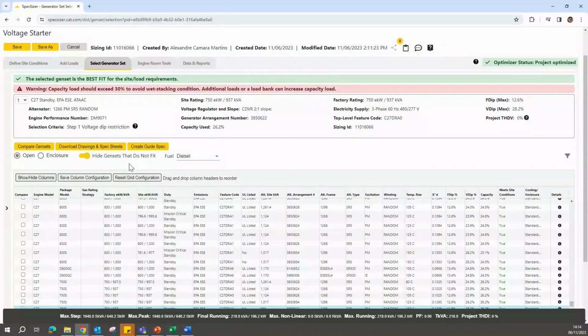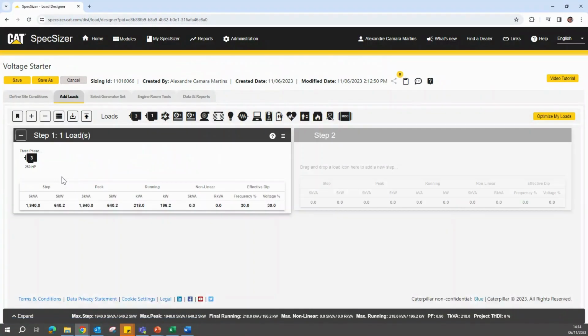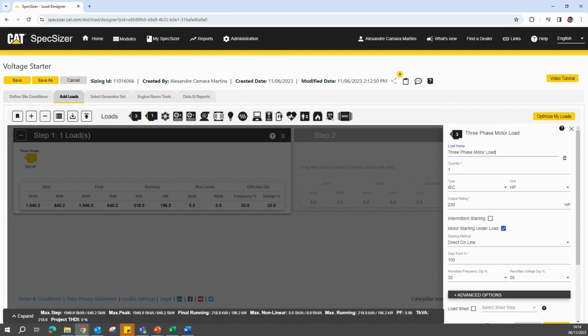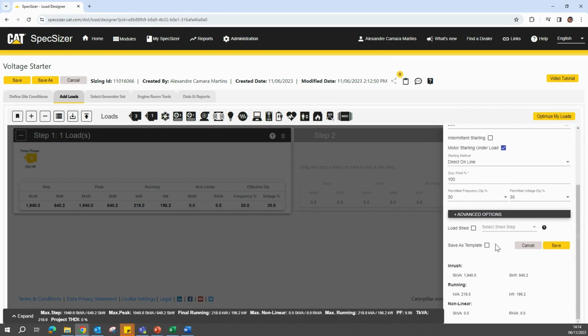Let's take a look at the loads added for this sizing example, more particularly the three-phase motor load. You can see here at the bottom of the load page the inrush of 1940 skVA. Comparing it to the running load of about 218 kVA, we can see there's a great difference between them.